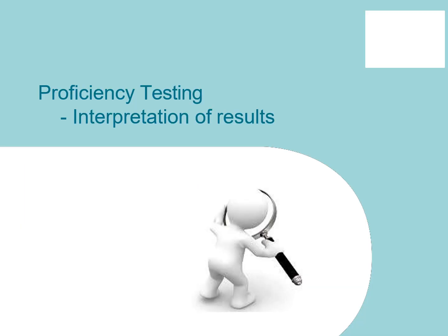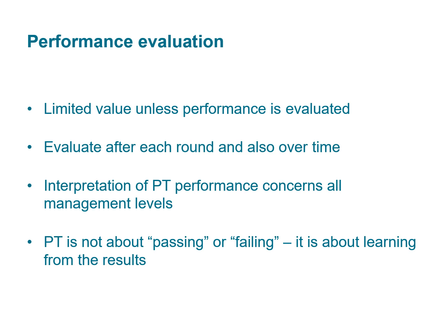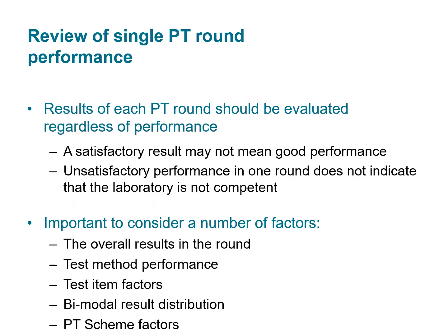So interpretation of the results. So class, performance evaluation. There is limited value unless the performance is evaluated. So evaluate after each round and also over time. Interpretation of PT performance concerns all management levels. So here, class, again, PT is not passing or failing, it's about learning from the results. So review of the single PT round performance. Results of each PT round should be evaluated regardless of the performance. A satisfactory result may not mean good performance. Unsatisfactory performance in one round doesn't indicate the laboratory is not competent. Probably they might be facing some other problem.